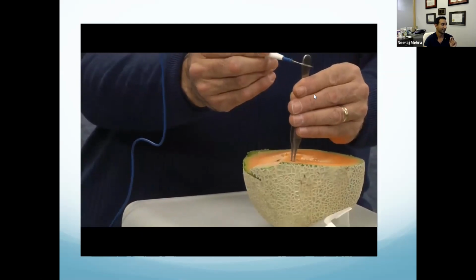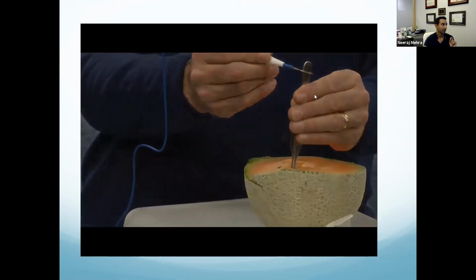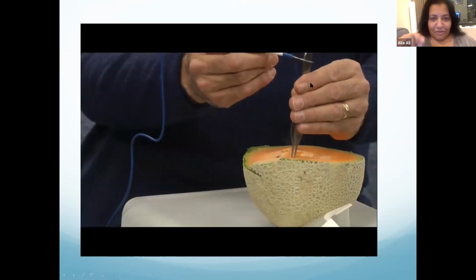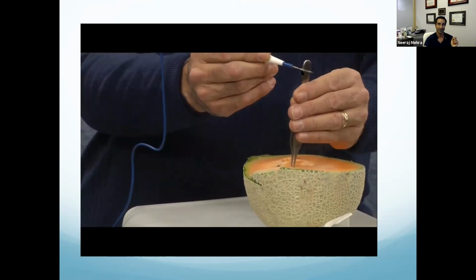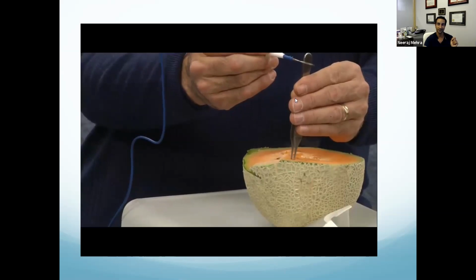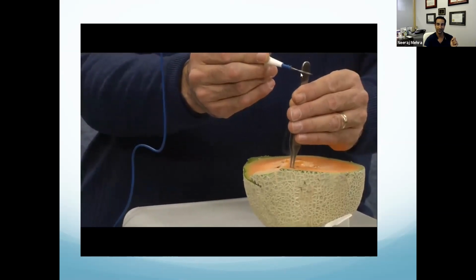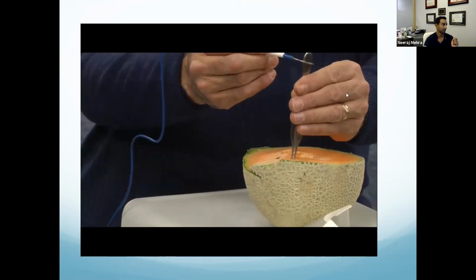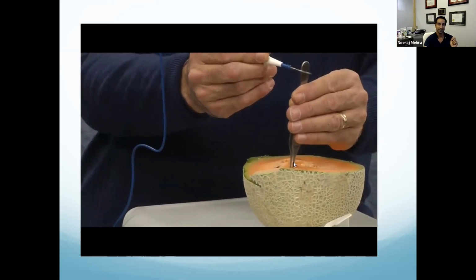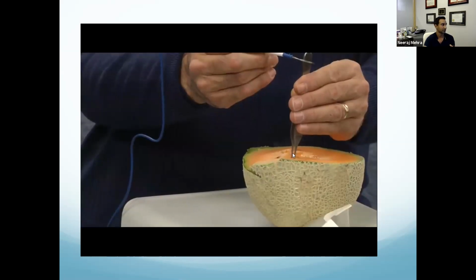Does anyone have any thoughts on that? Not touch above the hand. Touch it below. Right, exactly. So this is bad technique. Energy is going to flow through where there's least resistance. So if you start up here and it's trying to get through there, you create a bypass to someplace else where it wants to go, so it's going to go to your hand. Whereas if you start down here, it's closer to where it wants to go, which is through the patient. So when you're touching the instrument, you want to touch as close to your effective area as possible.